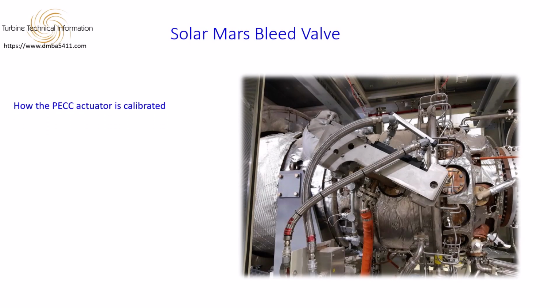How the PECC actuator is calibrated. Now, the part that causes real site problems. The closed position calibration. This actuator references everything from the mechanical closed stop. So the procedure matters. Back off the closed stop bolt. After energizing the valve, inject a 4 mA signal into the actuator. This drives the valve to the mechanical seat with force. Then screw the stop bolt in until it just touches the stop. That position becomes the zero reference for every other command. If that stop is wrong, every indicated position is wrong. And the control system will be doing perfect math on bad mechanical information.